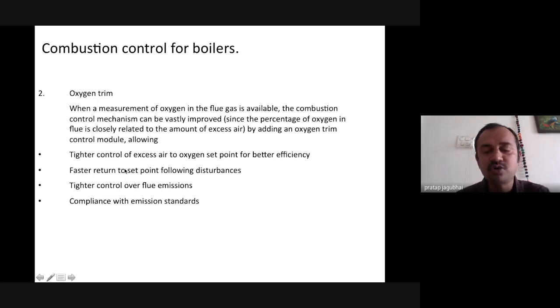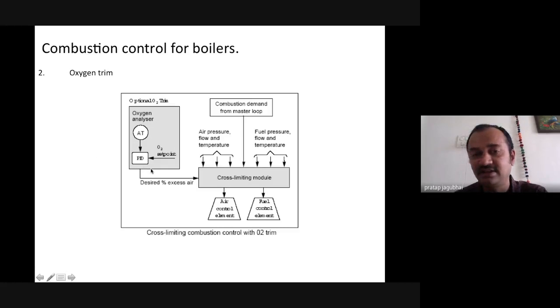So what to do for that? We need to have oxygen trim, and oxygen trim can be achieved with the help of an oxygen analyzer put outside the furnace, which senses the oxygen percentage from the combustion outlet and regulates the FD air inlet in such a way that tighter air control is always available.